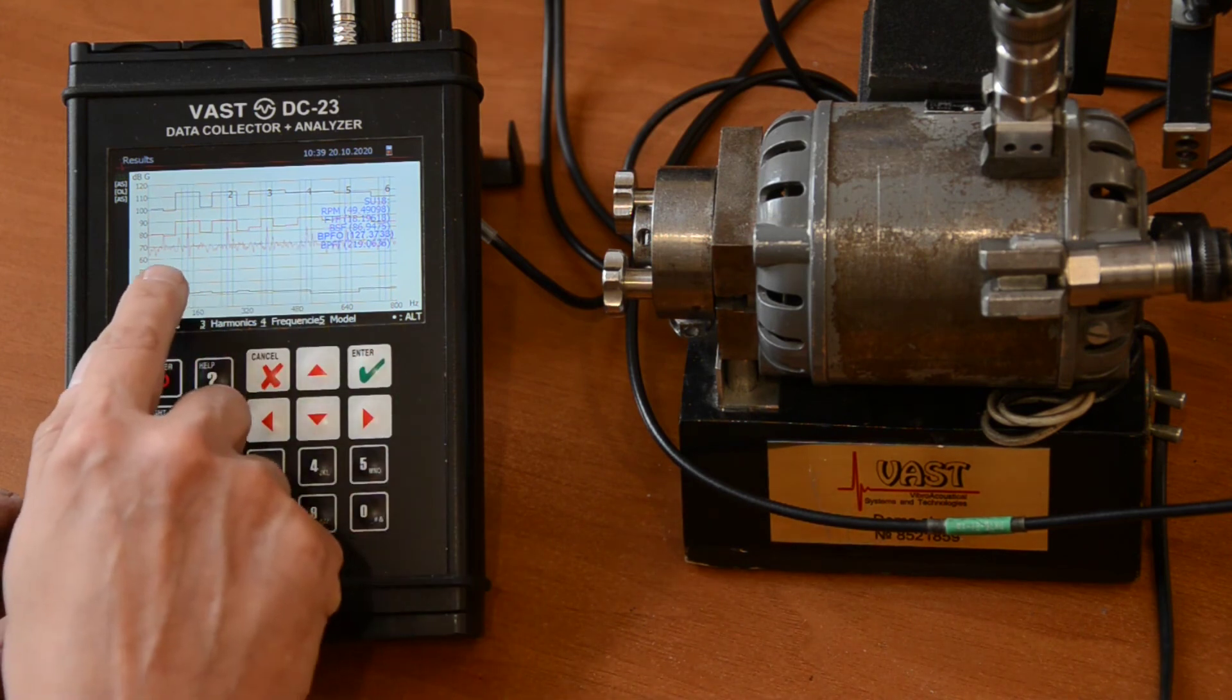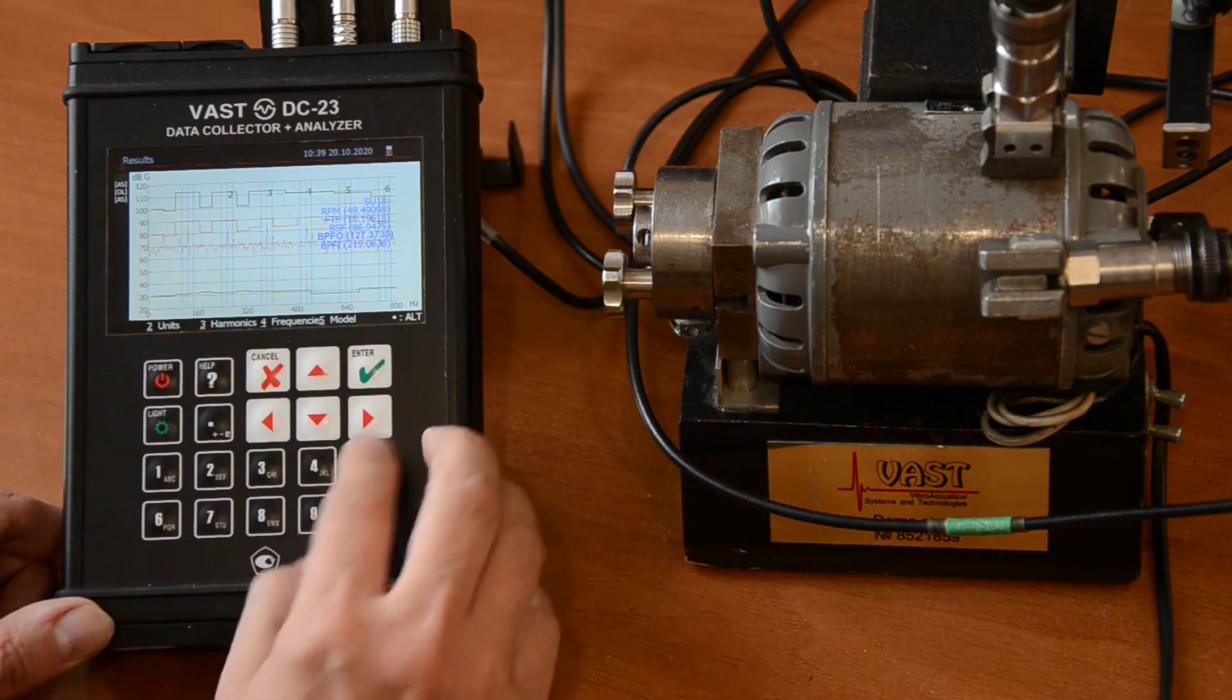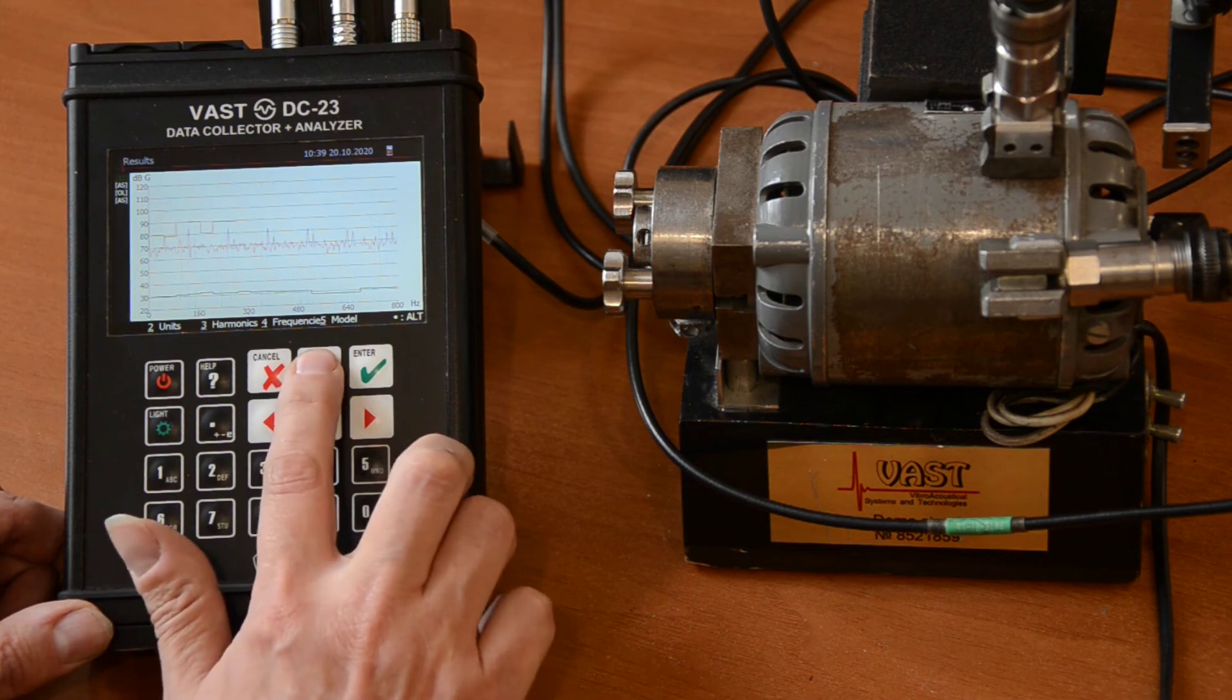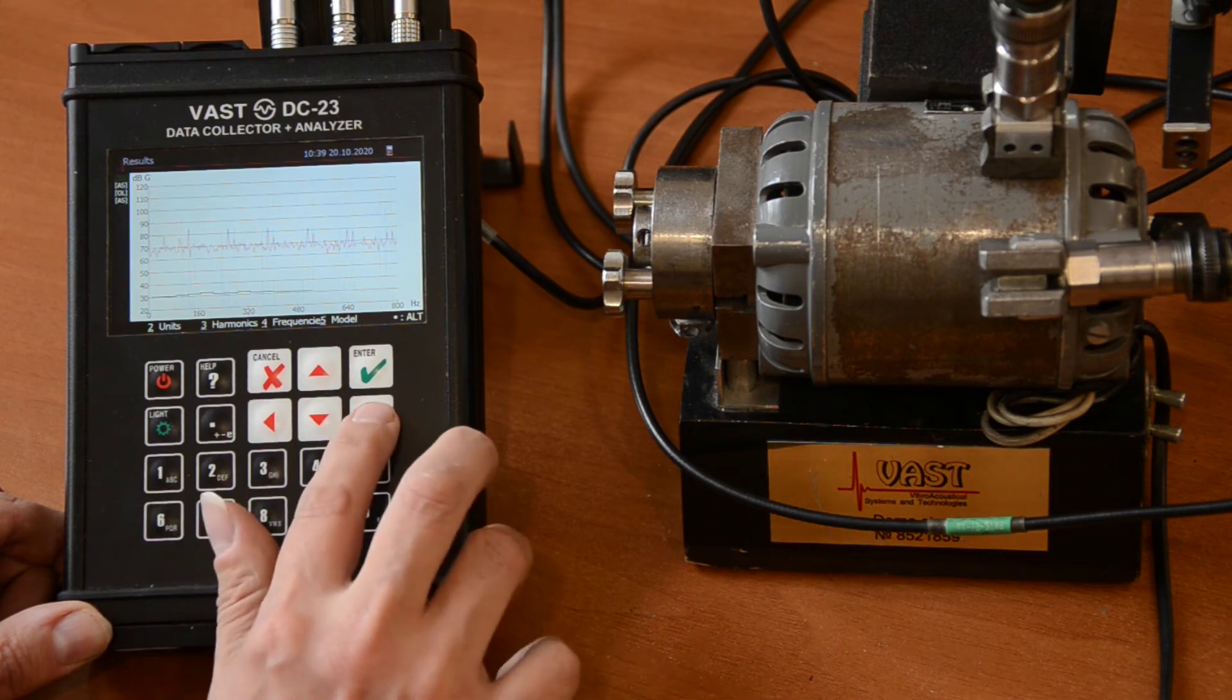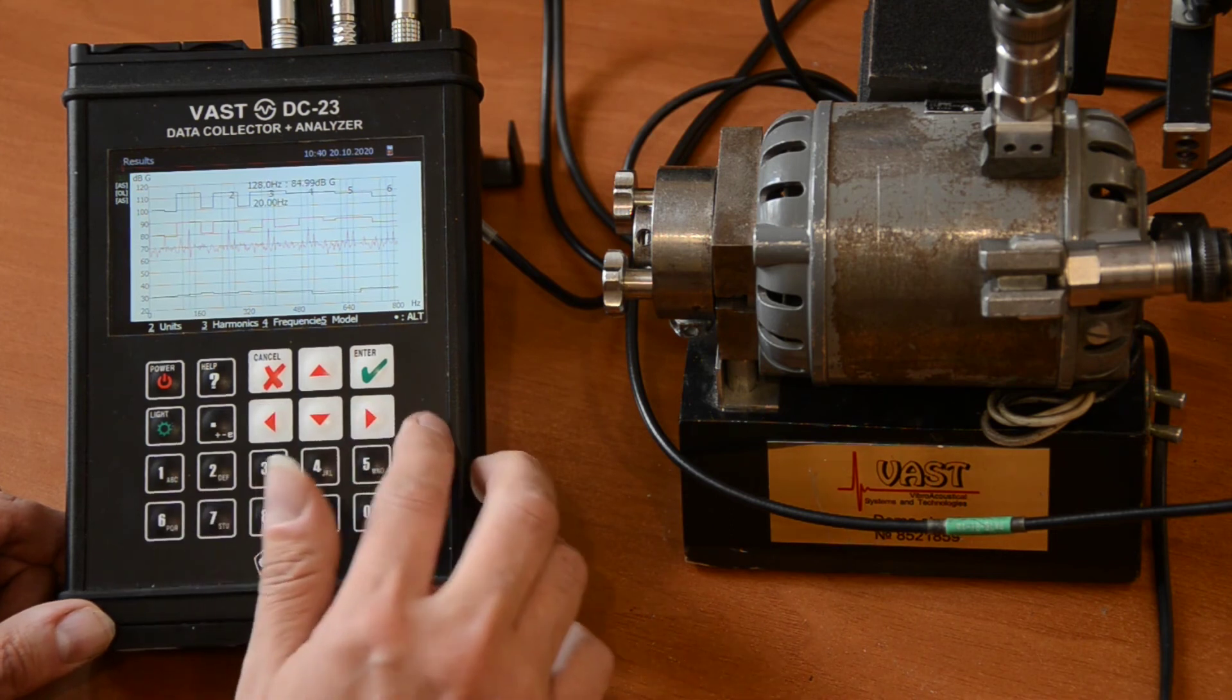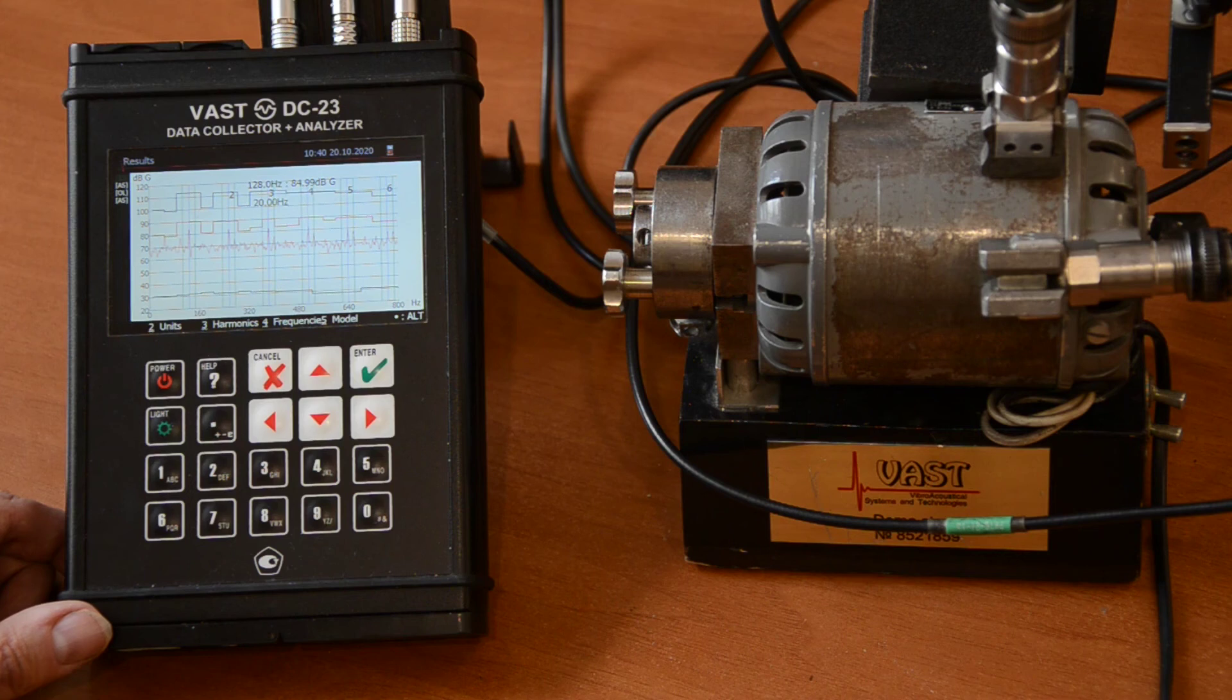So, we have actually some outer race frequency modulated by some frequencies. And this is BPFO. And this is FTF. So, we have a possibility to change the modulation. We can move the harmonic cursor. And this is actually an in-field analysis. So, for this very bearing, I would say that we have a problem of the outer race. We have a crack of the outer race. And we have a problem with the balls. If we have BPFO modulated by FTF, we can actually say that we have non-uniform size of the balls in this very bearing.